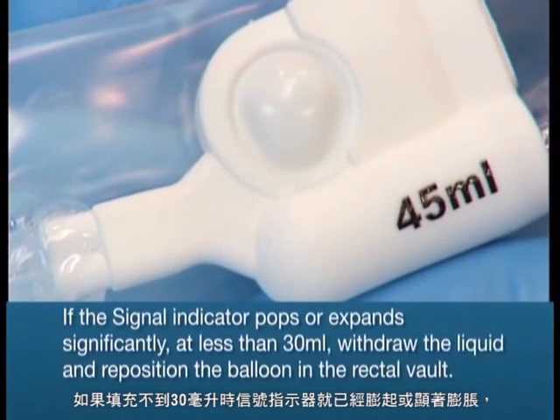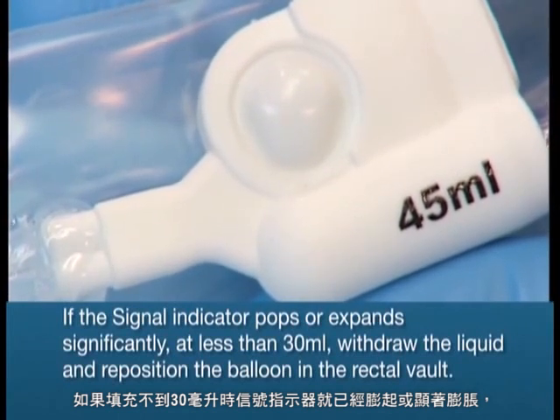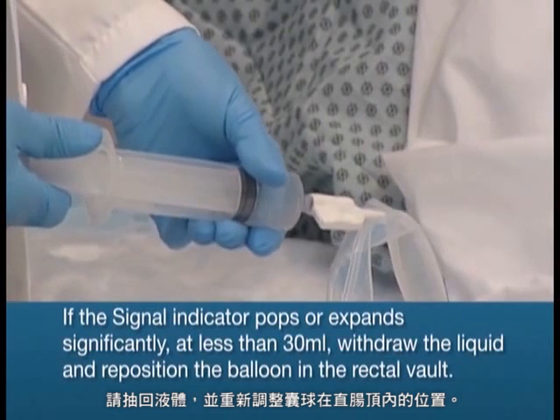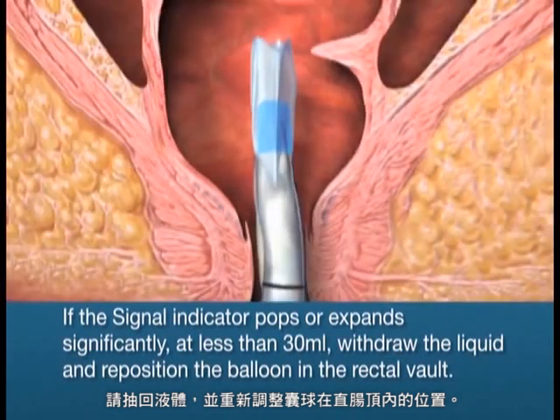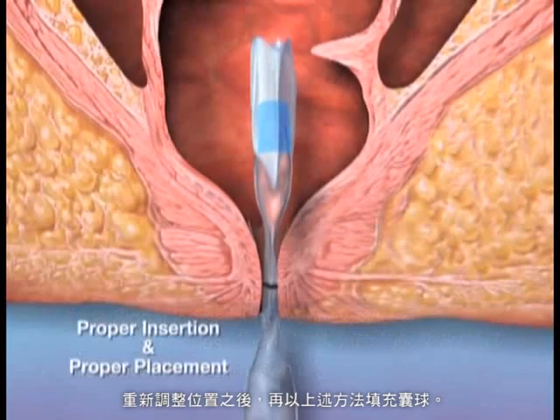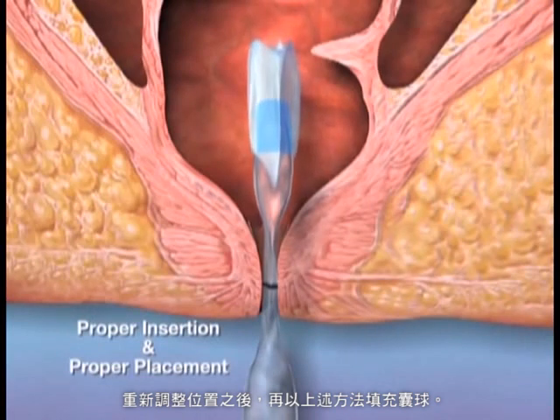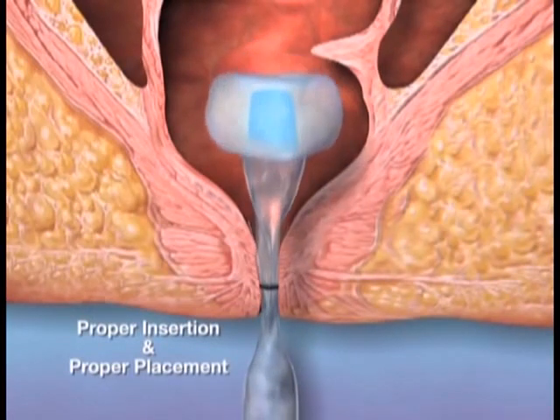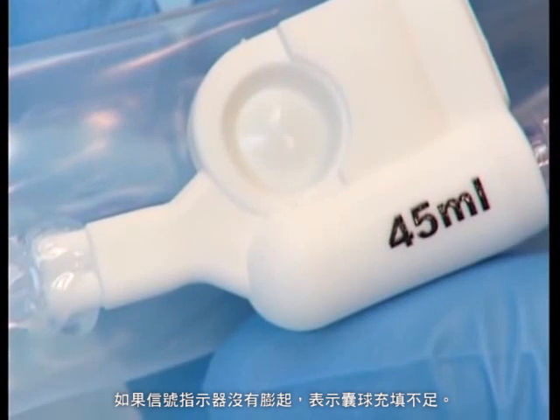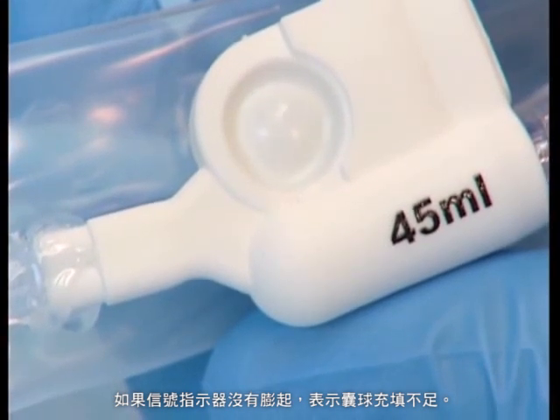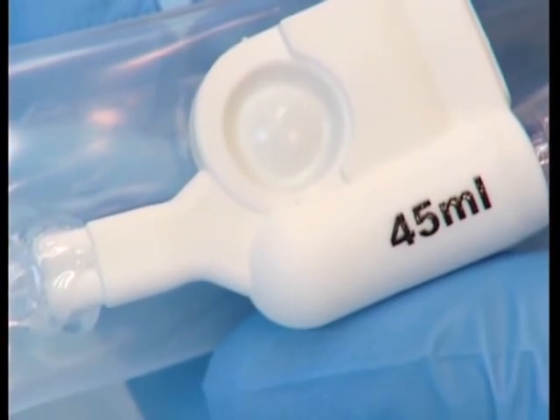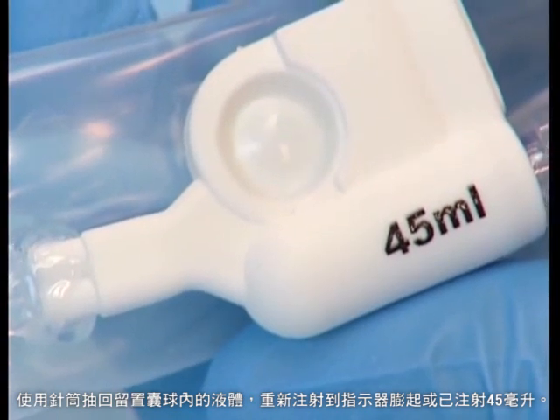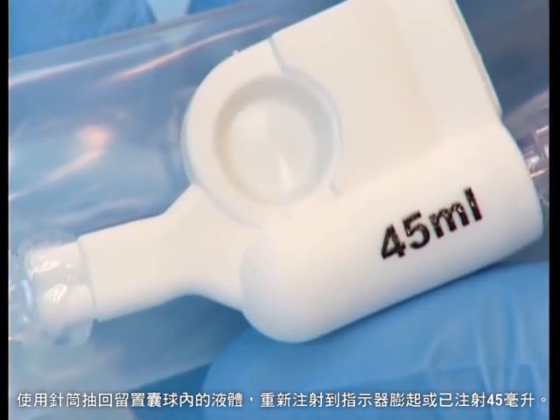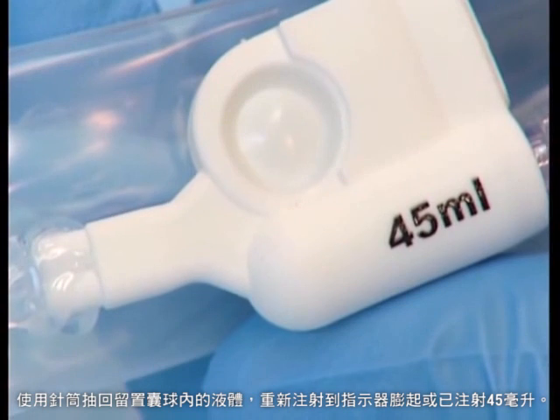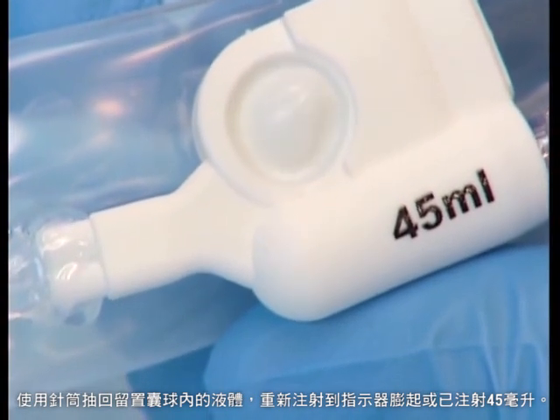If the signal indicator pops or expands significantly at less than 30 ml, withdraw the liquid and reposition the balloon in the rectal vault. After repositioning, fill the balloon as described. If the signal indicator does not pop, the balloon is underfilled. Use the syringe to withdraw fluid from the retention balloon and re-inject until the indicator pops or 45 ml has been injected.